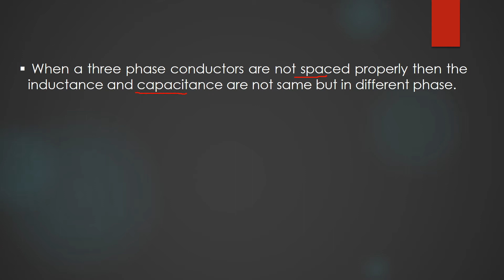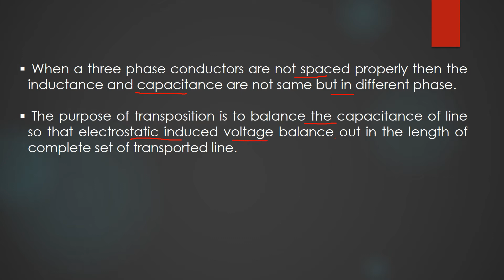When three-phase conductors are not transposed or are not spaced properly, then the inductance and the capacitance are not the same. Therefore, the transposition is being done. The general purpose of transposition is to balance the capacitance of the line so that the electrostatic induced voltage gets balanced out in the complete set of the transposed line.